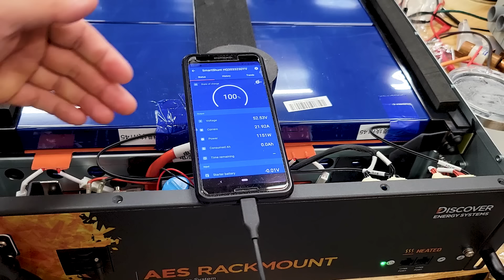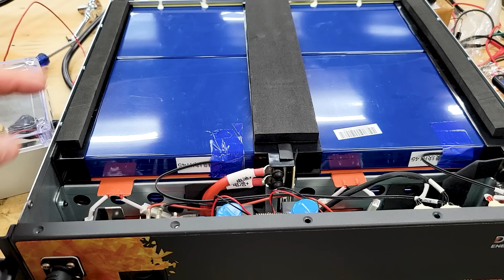At this point I think we're done with the testing. We've done the heating, the overcurrent, the capacity, and the continuous amperage test, and it passed all of the testing with flying colors, doing exactly what the manual said it was going to do. The relays and circuit breaker inside are all rated for 200 amps, so when they built this, they oversized all the components. They did a really nice job building this battery.